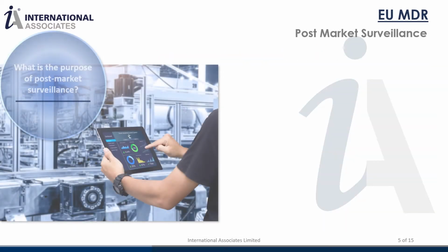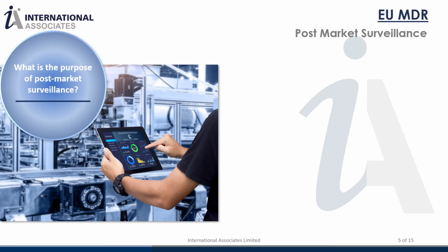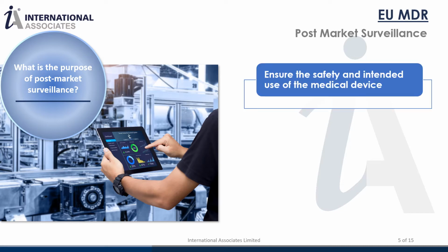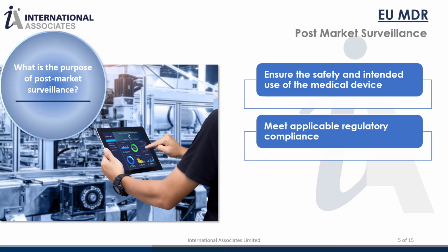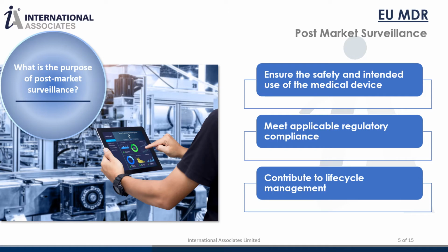So, what is the purpose of the post-market surveillance? The purpose of a well-established PMS system is the timely identification of risks that were not known until use, as well as opportunities for product improvements, all with the aim to ensure the safety and intended use of the medical device, meet applicable regulatory compliance, and contribute to life cycle management.